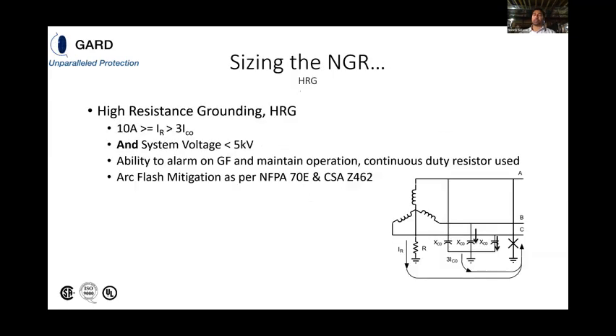So to summarize for you guys, let's say you've done a charging current calculation on your system and your system is below 5 kV. You realize that that charging current is below 10 amps. You size your let-through current of your resistor greater than the charging current, but less than or equal to 10 amps. That gives you the ability to alarm on ground fault while maintaining operation, assuming that you're using a continuous rated resistor. You're also satisfying arc flash mitigation as per NFPA 70E and CSA Z462.